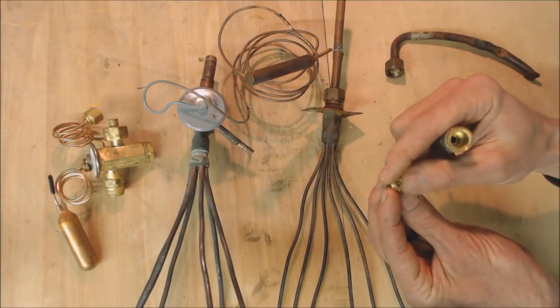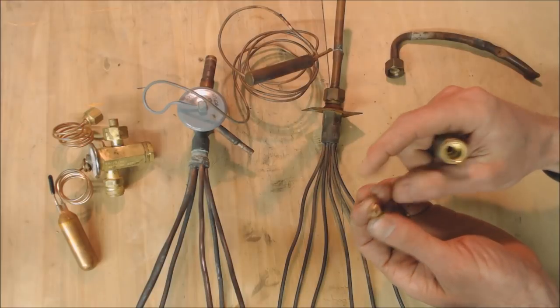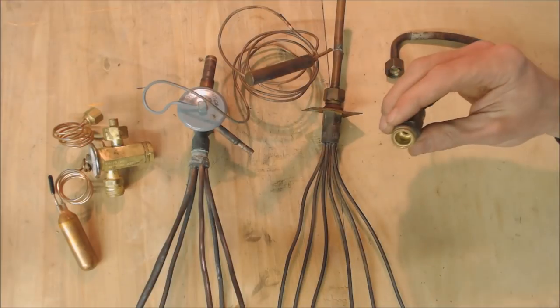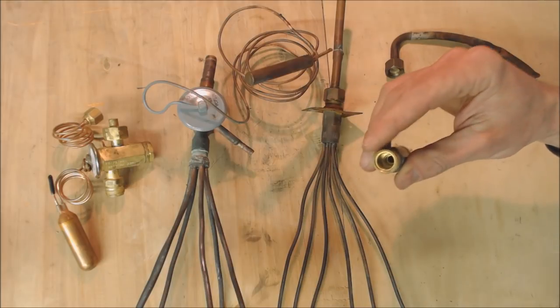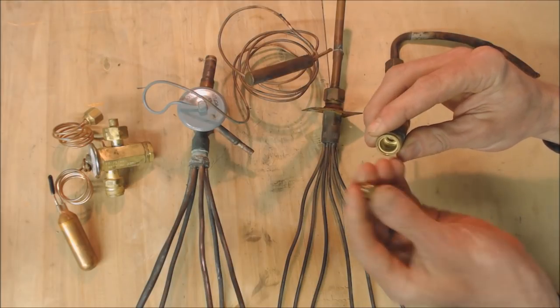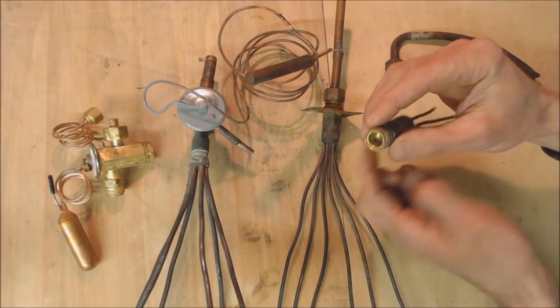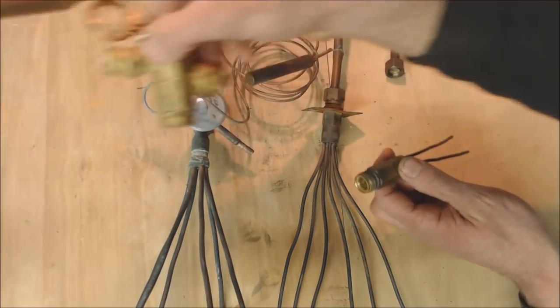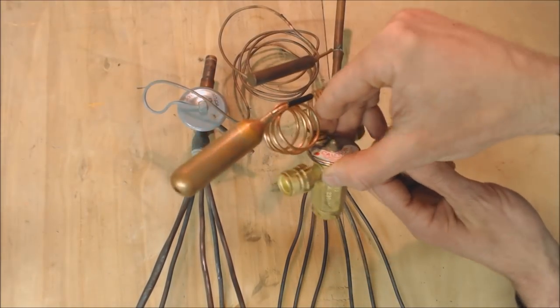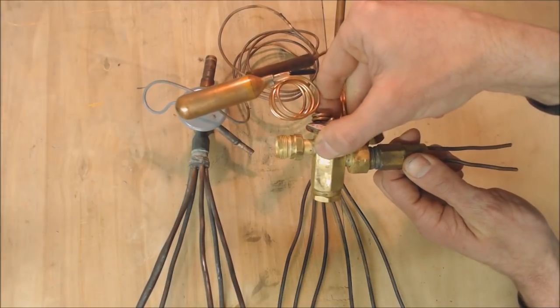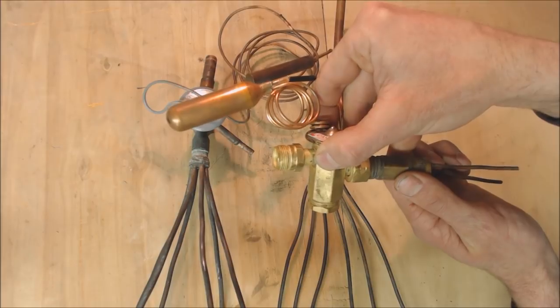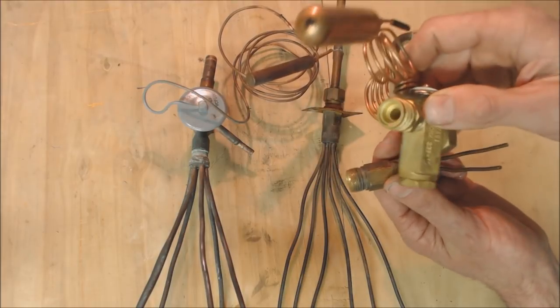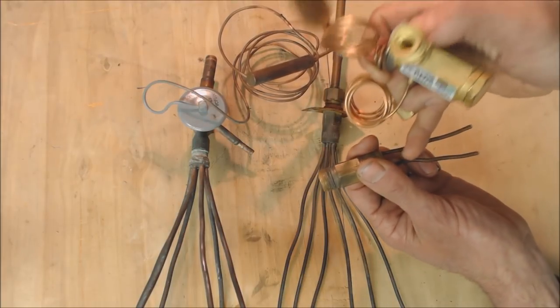This allows a bypass and easy access to change a piston size. A piston chamber also allows you to install a TXV instead of a piston. If you take the piston out, you can use a TXV such as this one and have that get connected together. So then you have your TXV and you still have your distributor tubes connecting to the evaporator coil.